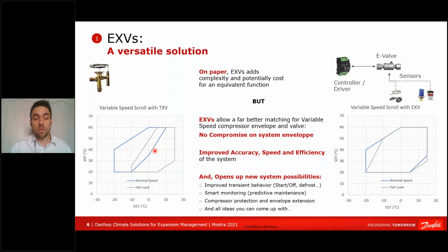At some point, you have to make a compromise, whether you want to reach some of the points at high speed and some of the other points at low speed. Don't get me wrong, that may be sufficient for many applications. That's why TXV still has a very good value proposition for many applications.